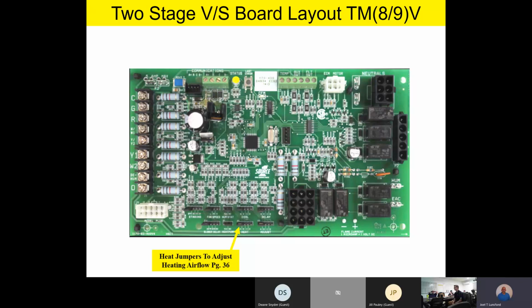Remember, team, we always ship it on the highest airflow possible because we don't know what the condition of the duct system is going to be. So during your startup and commissioning, you may want to adjust that a little bit. Instead of blowing a huge amount of air, you maybe want to lower that airflow a little bit for comfort. But again, make sure and look at that data plate on the service panel of your furnace. Do a temperature rise measurement, and then set up your airflow so it falls right in between our temperature rise. Typically on our data plate, you're going to notice a pretty wide range. The temperature rise on the data plate will be somewhere between about 40 and 70 degrees. If you set that up to where it's right in the middle, you'll be exactly where we like you to be on the furnace. Any questions or comments on the jumpers we've talked about so far? Everybody good? Okay.